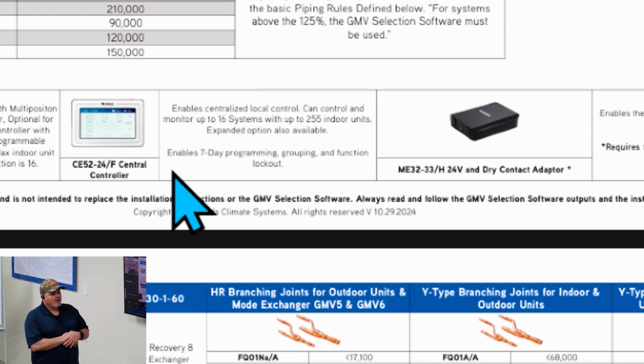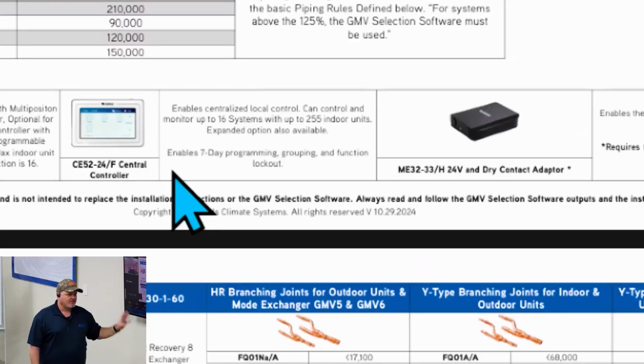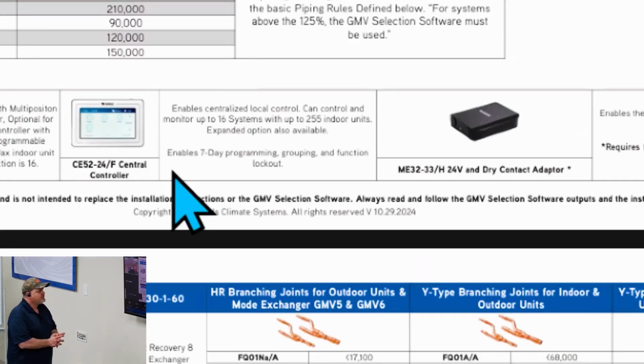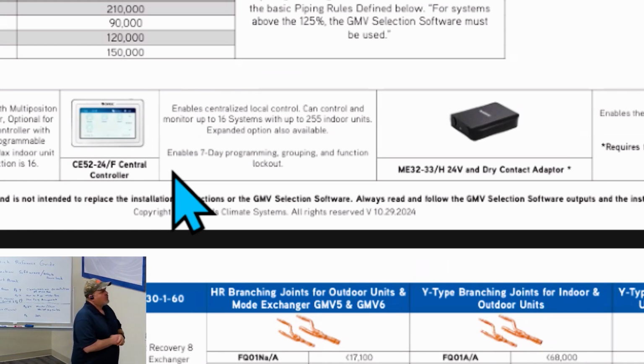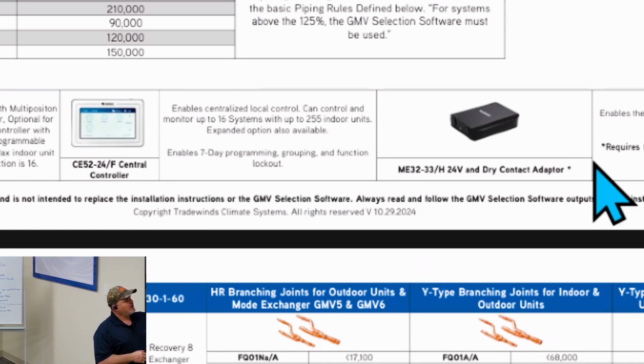If you happen to see a C5 error code on your wired controller or your centralized controller, that's exactly what it means: you have duplicate addresses and it wasn't done properly. Again, if you just refer to the central controller instructions, it talks about the dip switch settings and everything. Whether you're using central control or Cool Automation, the wiring and those dip switch settings are exactly the same, and we'll cover that coming up.